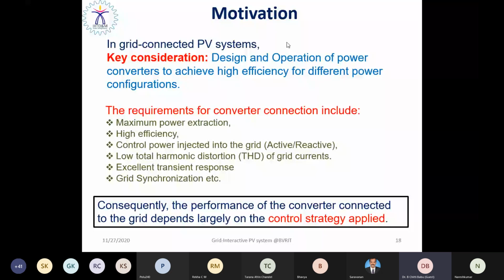Due to the variable output power, it cannot be directly connected to any electrical load or any electrical grid. Ultimately, they do not accept variable output power or variable current and voltage across any kind of load. That is why we have to use a power converter: as it has intermittent characteristics, it cannot be directly connected with the utility grid, so we have to use a power electronics converter. Power electronics converters play a very major role in integrating a solar PV system with the utility grid. All renewable energy sources are intermittent in nature and have an inherently variable output power, so they cannot be directly interfaced with the utility grid. We need an interfacing device called the power electronics converter.